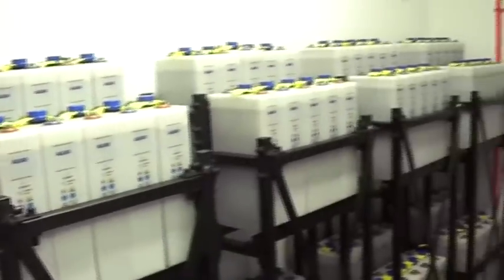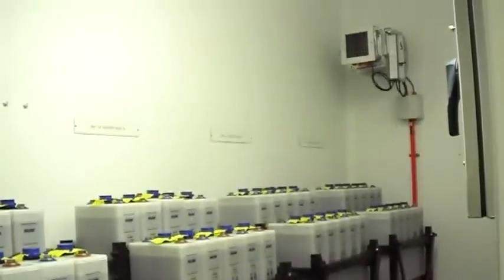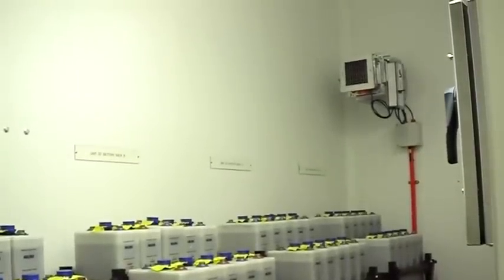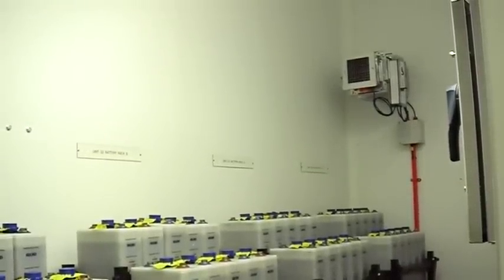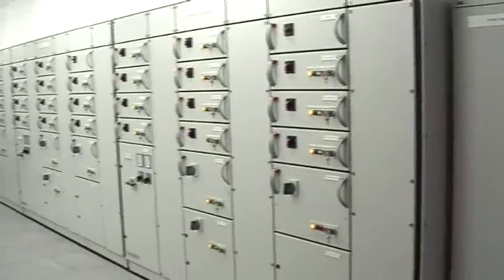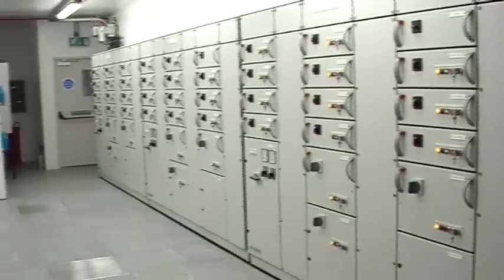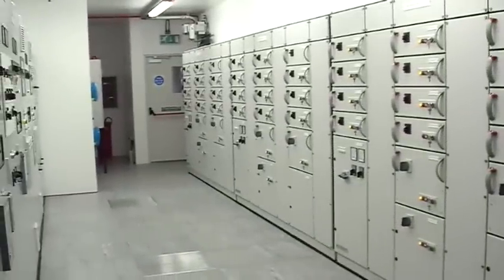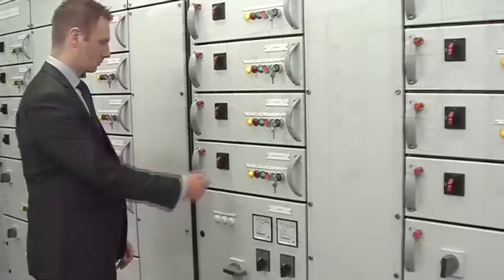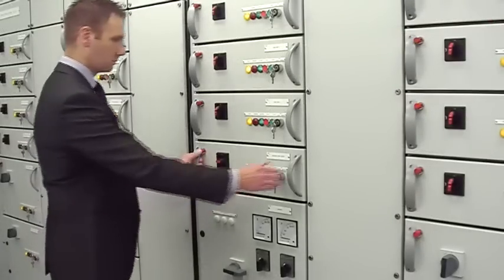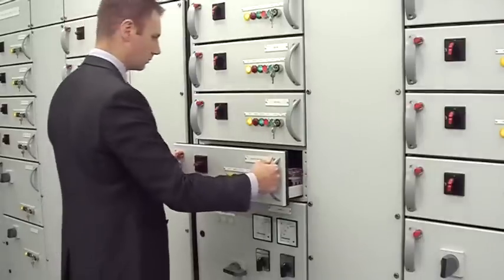A dedicated battery room contains the dual redundant battery racks that provide the gas turbines with enough power to run the DC lubrication systems in the event of a mains failure. 400-volt motor control centres provide the power and control of the turbine package auxiliary systems, such as cooling fans, lubrication heaters and the turbine starter motor.